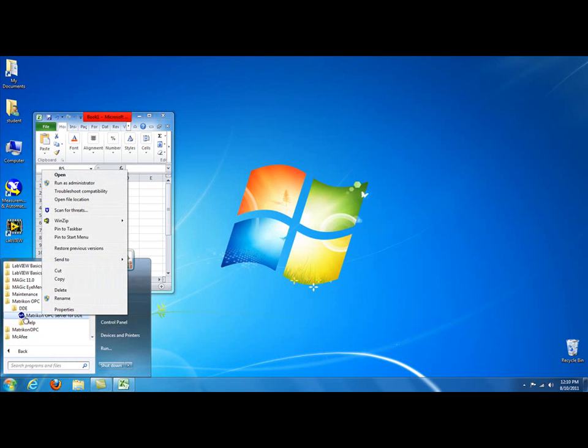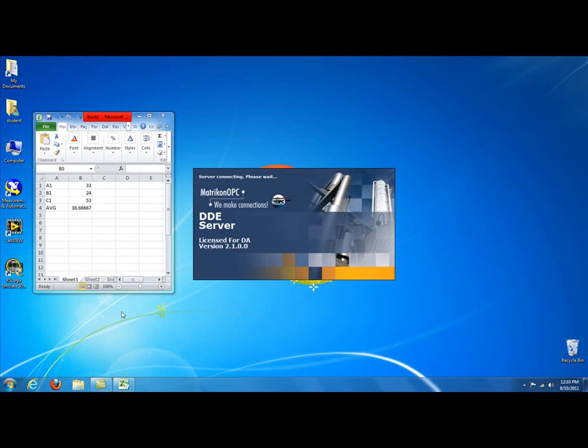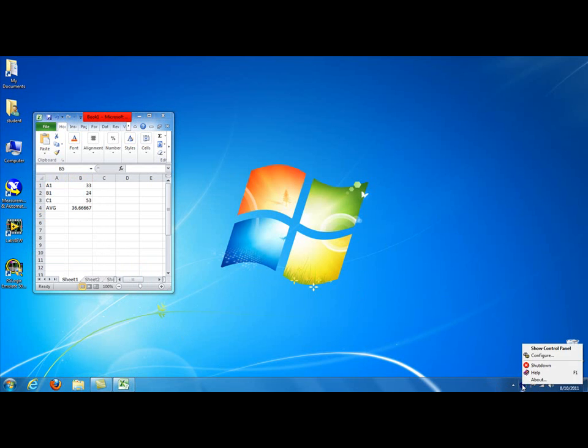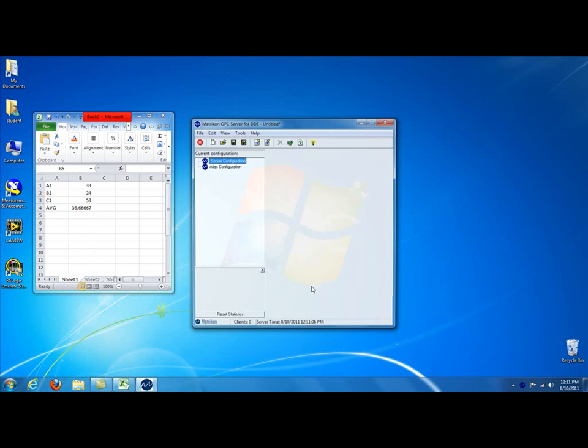Then you come back and you run the program. The other way to do it is to always click up here and run as Administrator. I've already set it in Properties, so it's not going to really make a difference. It's going to run as an Administrator regardless of which way I click on it. Once you run as Administrator, if you install this as a program and not as a Windows service, you would notice that the Matrikon OPC server for DDE, the icon shows up on the taskbar. You do a right-click and click on Show Control Panel. That should tell you that the server is now running between here and DDE, not necessarily this Excel spreadsheet. We'll have to configure that, and you have no clients connected. So, let's configure the server.